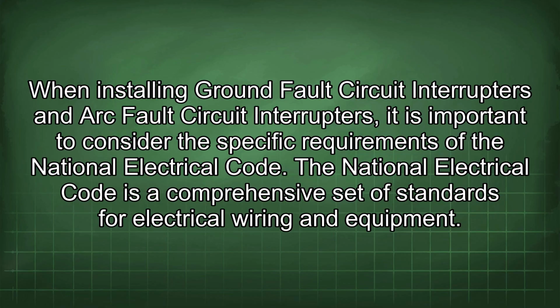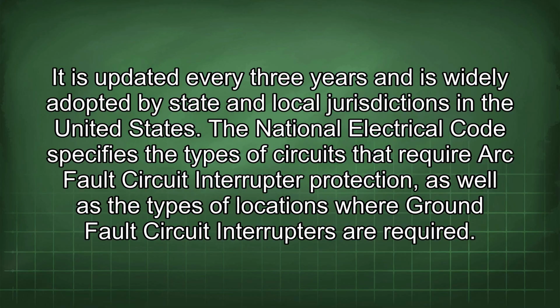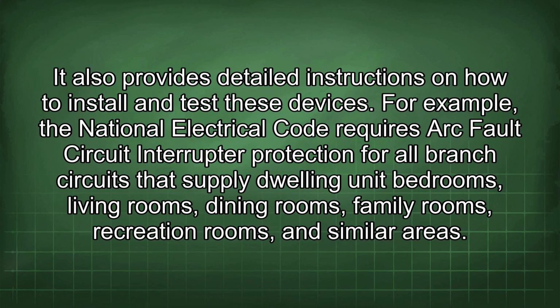When installing ground fault circuit interrupters and arc fault circuit interrupters, it is important to consider the specific requirements of the National Electrical Code. The National Electrical Code is a comprehensive set of standards for electrical wiring and equipment. It is updated every 3 years and is widely adopted by state and local jurisdictions in the United States. The National Electrical Code specifies the types of circuits that require arc fault circuit interrupter protection, as well as the types of locations where ground fault circuit interrupters are required. It also provides detailed instructions on how to install and test these devices.